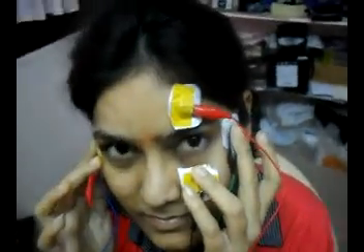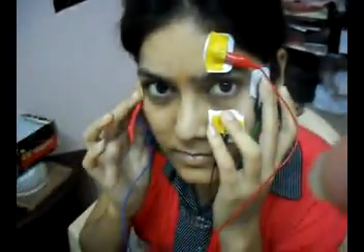Now I'll show you the placement of the electrodes. This is the electrode placement. So 2 electrodes are required, left and right, and 2 electrodes are required for up down. The same electrodes will detect the blink movement also.